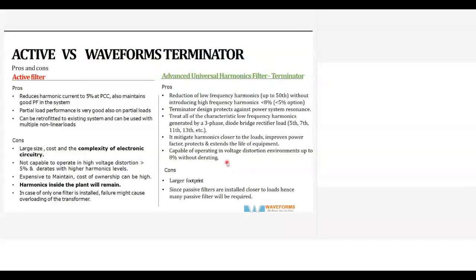The design protects against power system resonance. The capacitor installed in the filter is very small, so even at low loads there is no overcapacitance and consequently no resonance. It treats all the characteristic low order harmonics generated by a 3-phase diode bridge rectifier: 5th, 7th, 11th, 13th, all the harmonics. It mitigates harmonics closer to loads, improves power factor, and protects and extends the life of the equipment.